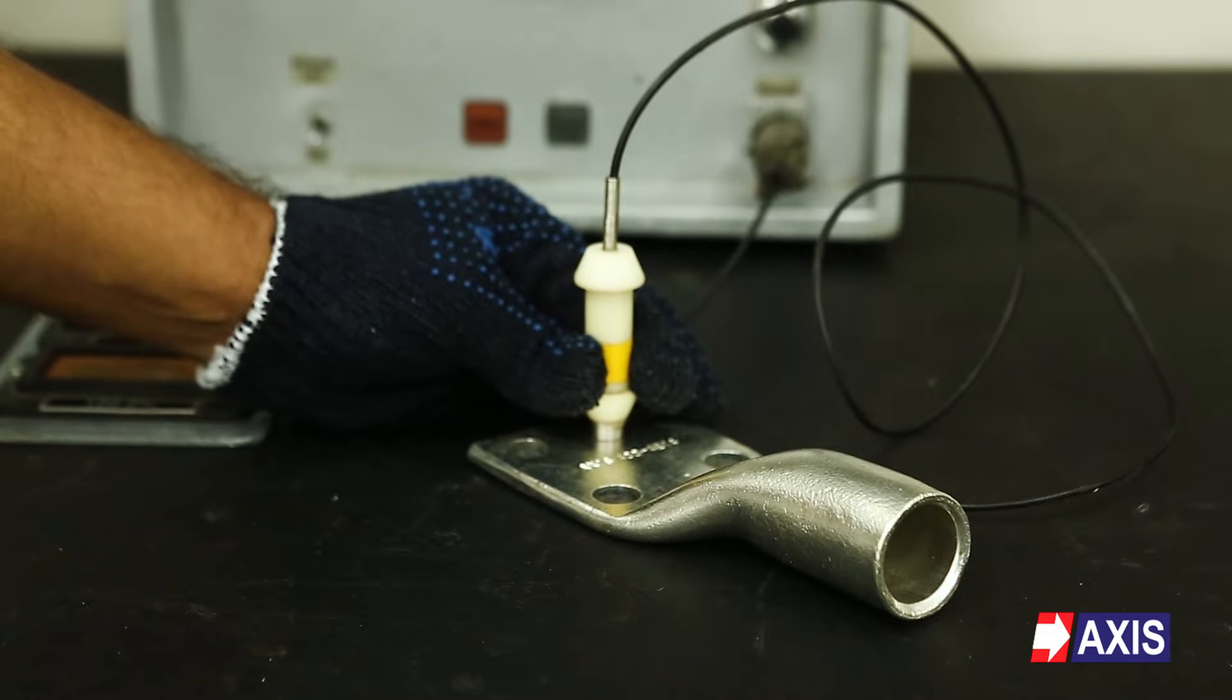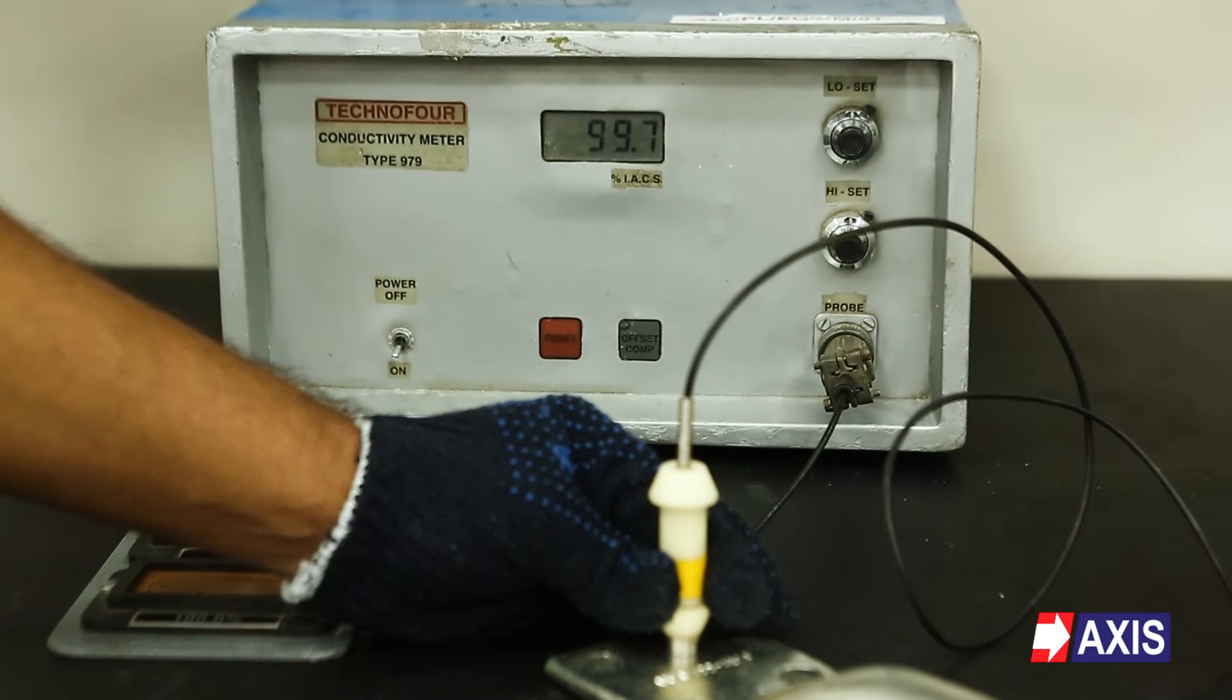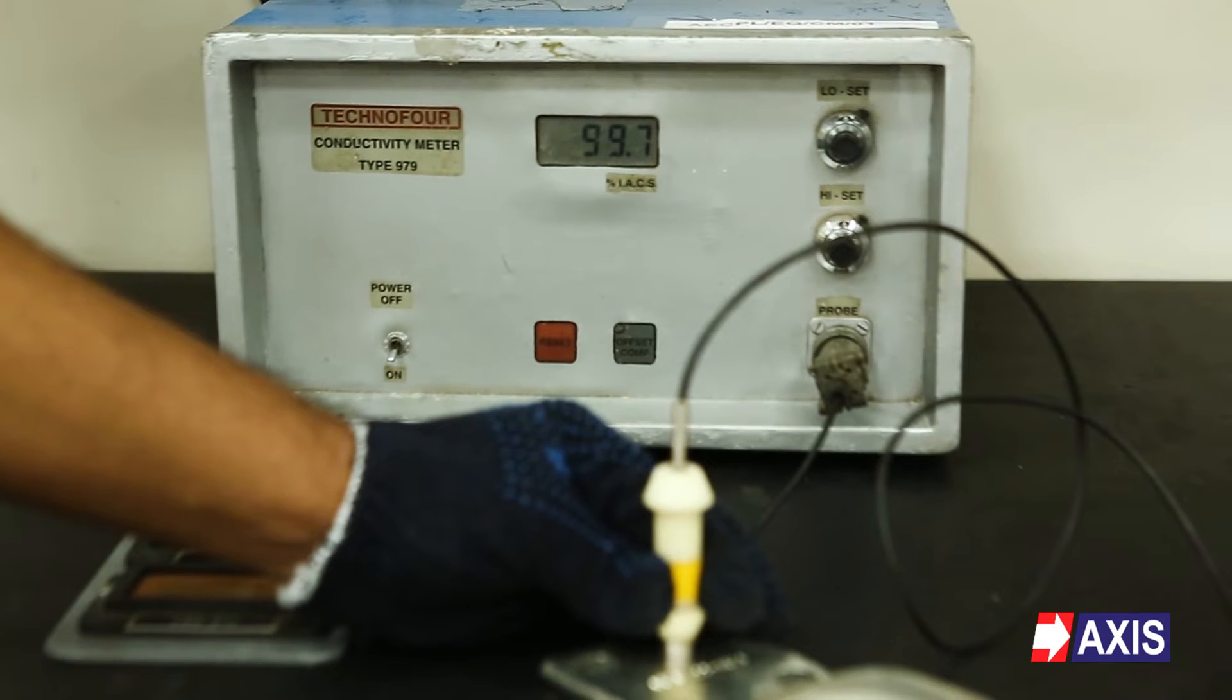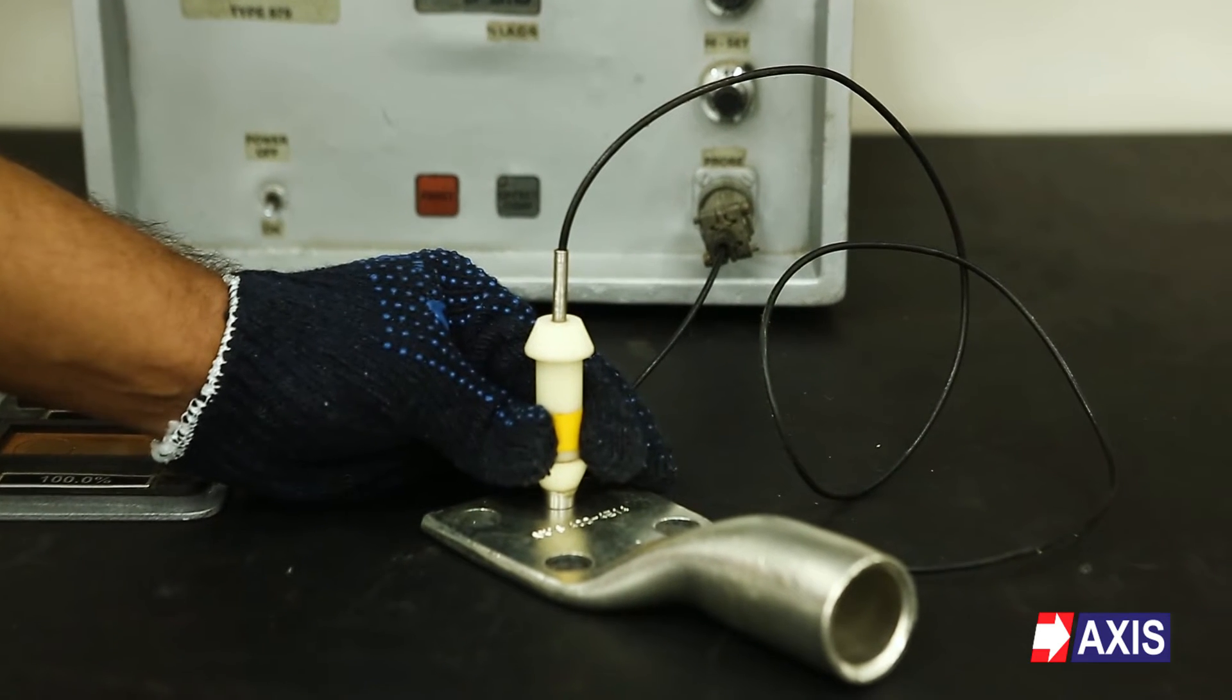We can also see that the Axis copper lugs have an electrical conductivity of 99% IACS. This indicates the raw material used to manufacture Axis cable lugs has high conductivity and uses pure copper material.